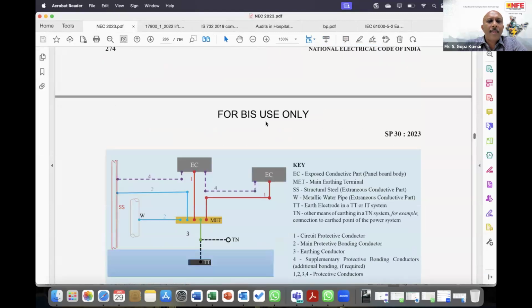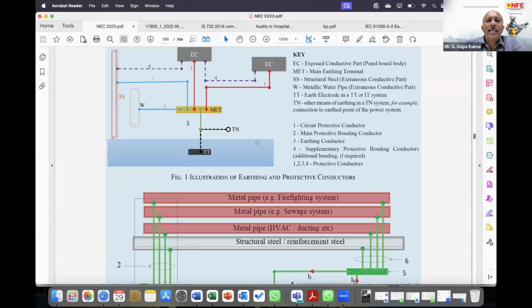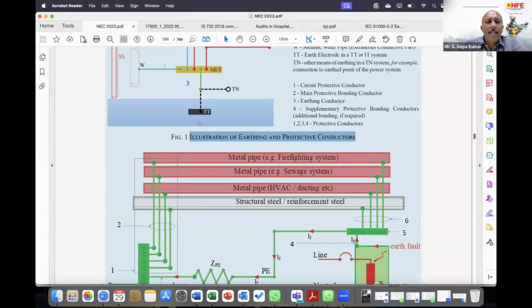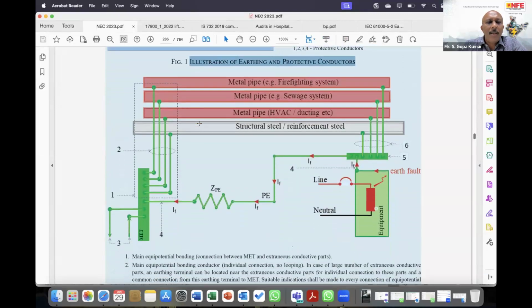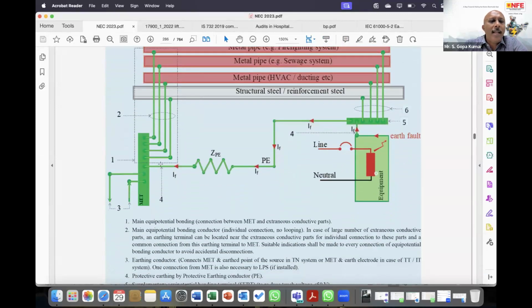You look at this figure. The first one: illustration of earthing and protective conductors. This is how you should make the protective equipotential bonding. Now if you look at the second one, on the left side you can see the main equipotential bonding, and then the secondary equipotential bonding. The earth fault, IF, is the fault current going through the PE conductor, ZPE.